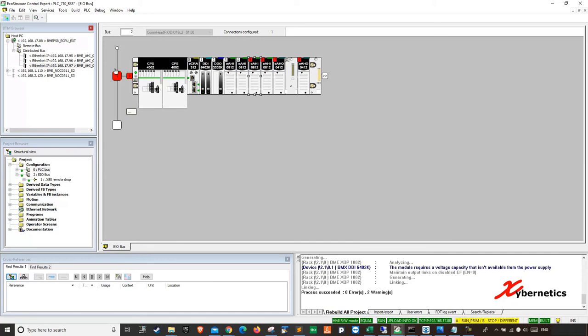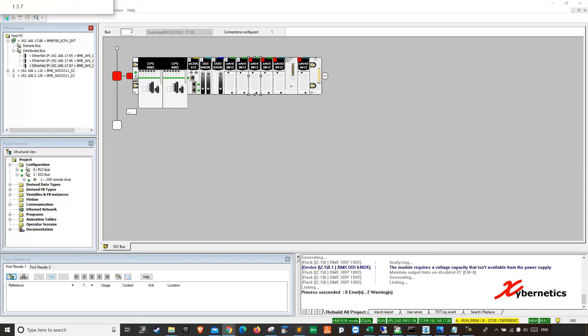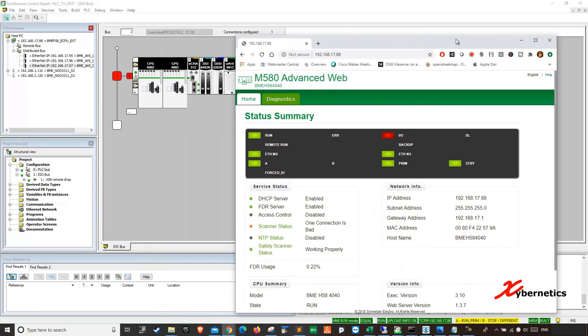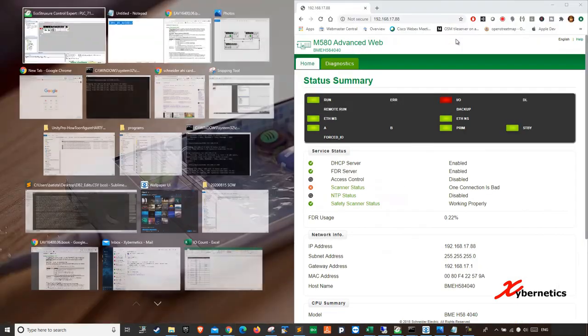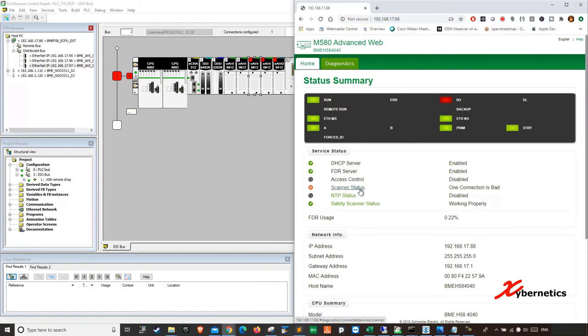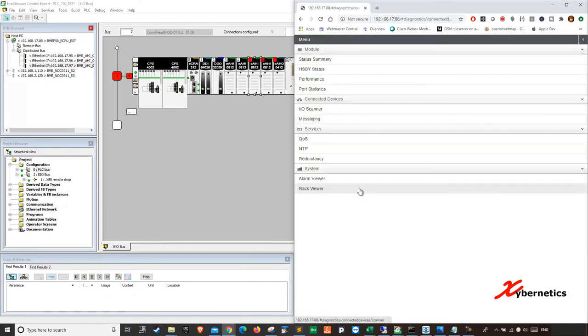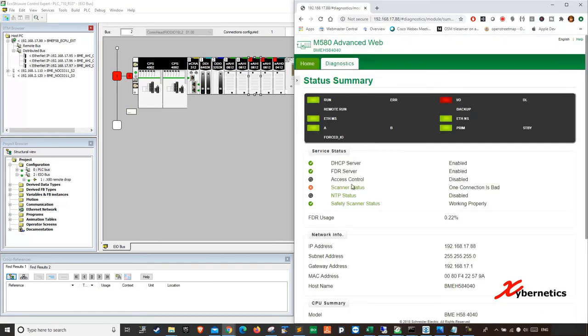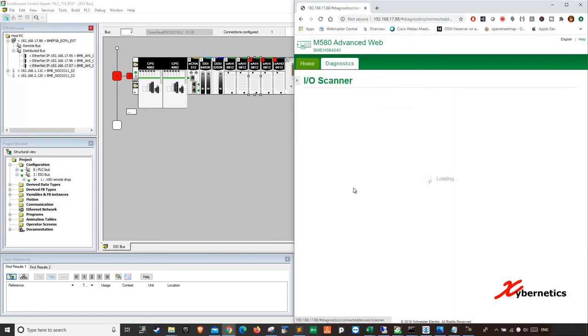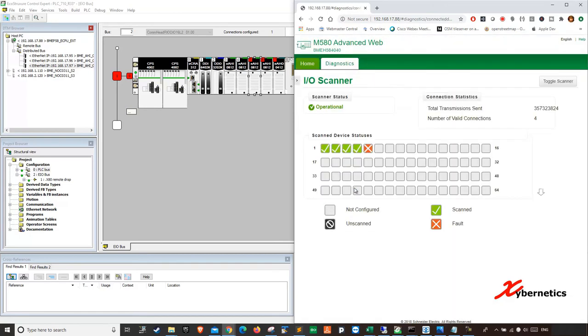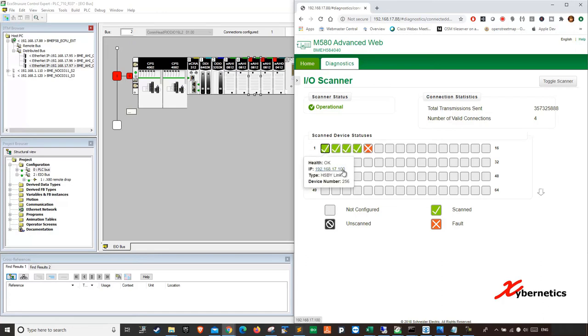This rack is one way to check whether your IO card is working or not. I'll show you another way you can actually check. Open your trusty browser and then enter your IP address of your PLC on the URL spot here. And you'll bring it to this screen here. So on this screen here, you click on scanner status. And you'll show you all the connections that you have right now, the Ethernet connection. So the first one is your CPU. How do I know this is CPU?